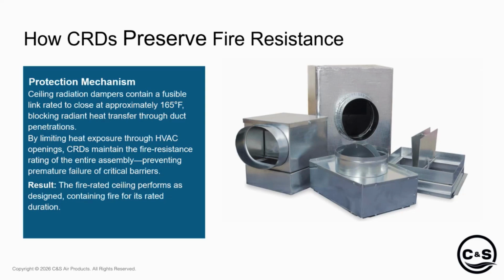How CRDs preserve their fire resistance. This is actually the mechanism of how they operate, not just the requirement by the code. When a fire gets started in the apartment space below, at a certain temperature range, I think the average fuse link lasts till about 155 or 160 degrees. At that temperature, there's a soldered link, and you can see it in this picture in the middle. That's our RD 521 BT, or the one to the right, the RD 521 NP. There's a fuse link holding two blades together, and as the temperature rises, the solder on the fuse link weakens, and then at a certain temperature point, the solder completely snaps, closing the blades and protecting the space above.